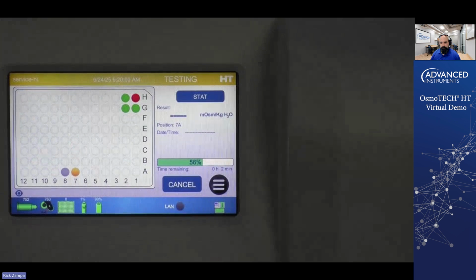And once we get up into the 70% range, you'll hear a knocking sound, or maybe you won't. But what that is, that's the crystallization of the sample. So what we're doing now is we're driving the sample down through its freezing point, down to a set temperature in the instrument. Once we get to that set temperature, we initiate the crystallization of the sample. All the time we're below this freezing point, the sample is liquid. That's why we initiate the crystallization. That causes the sample to freeze, goes up to its true freezing point. We then measure that freezing point, convert that to osmolality, and display that on the screen for you. So we're at about 82, 83% here. We should be finishing up our test here shortly.